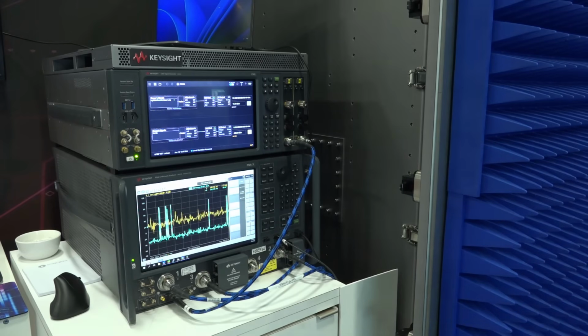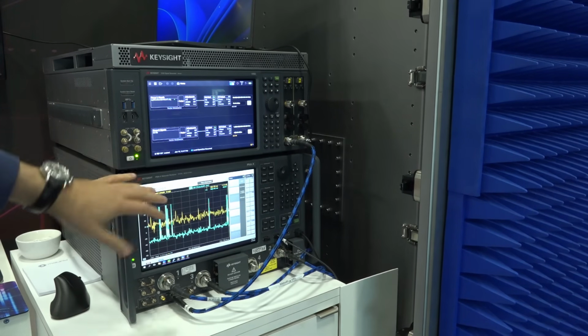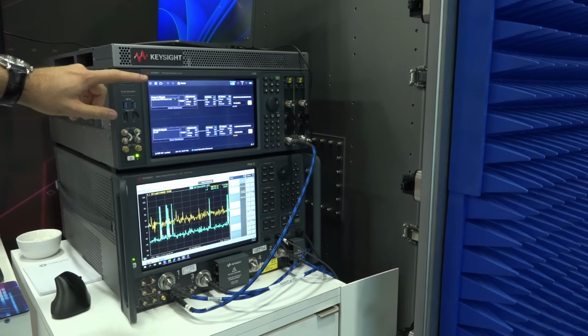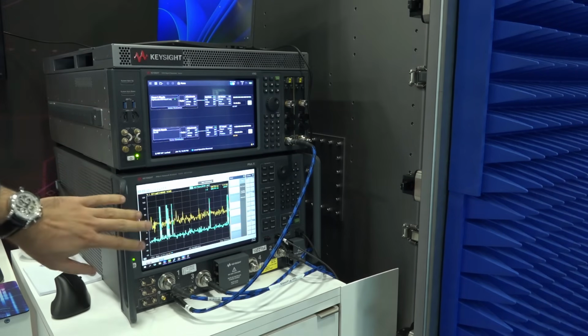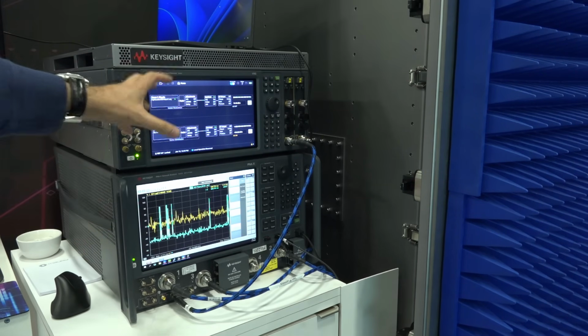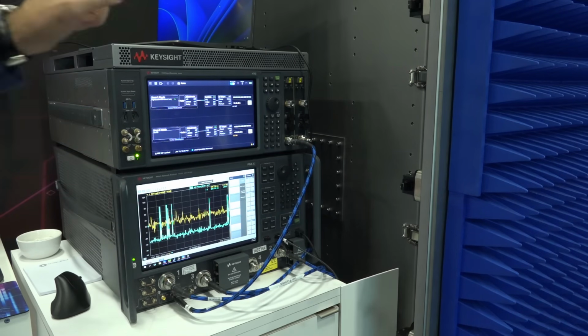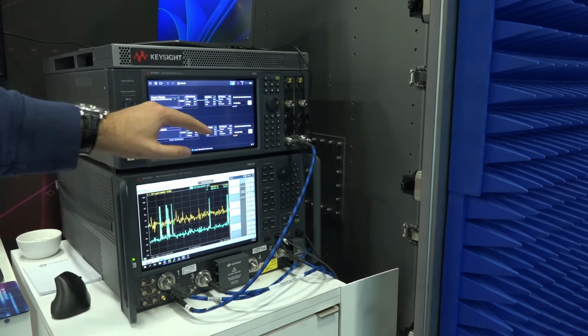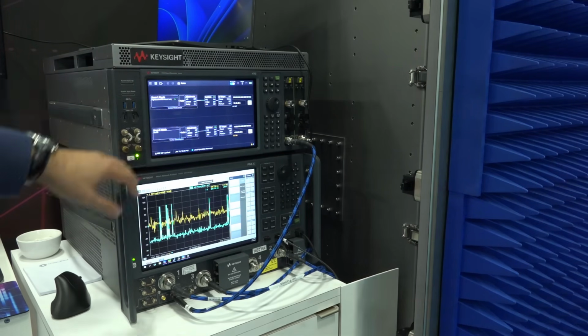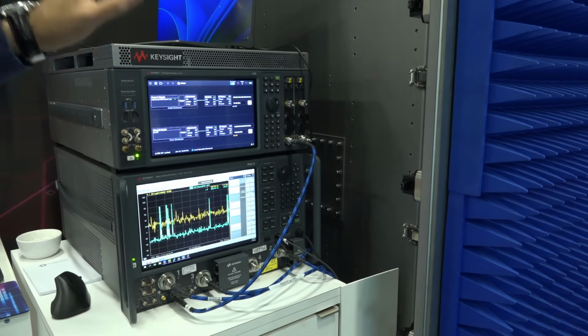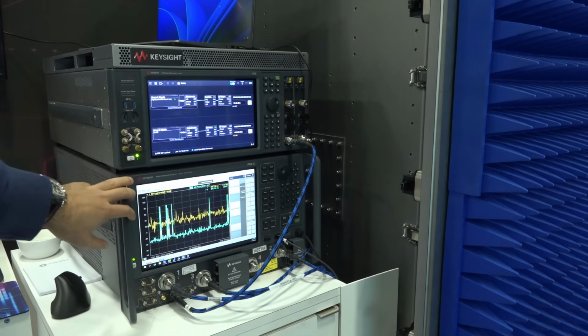And here are some of the devices that are coupled with this chamber. Of course, you have a PNAX for S-parameter measurement, calibration and everything. And here's also a VXG. Now, coupling the VXG into this device allows you to do modulations up to much, much higher instantaneous bandwidth. Now you can excite your device under test at the calibration plane that you want using high order modulation. Now you're looking at dynamic characteristics of the device during beamforming, all inside of the chamber in an isolated environment.